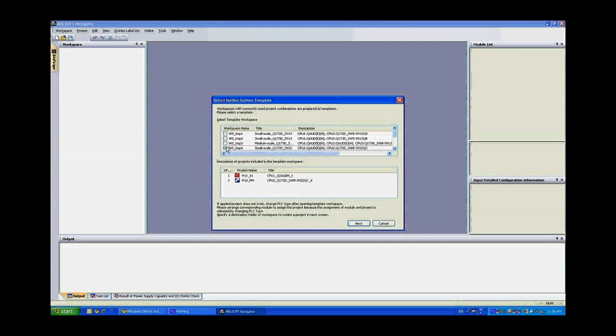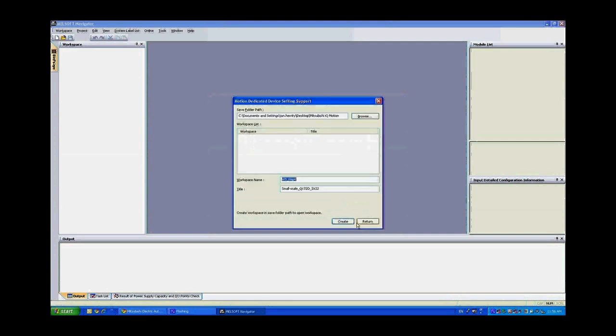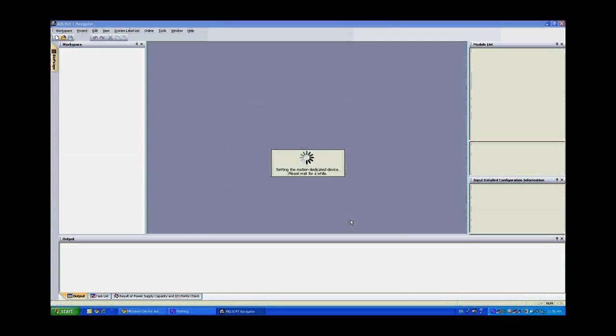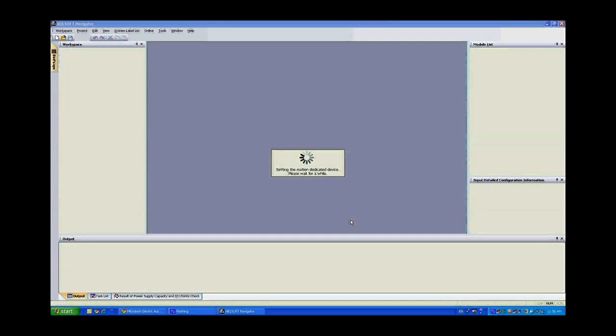WSTemp4 is a small-scale Q172D eight-axis motion controller template with a Q26UDH CPU. If I click next, this is going to generate two different projects, a PLC project and a motion project. It assigns all the dedicated labels for all the transfer between the motion controller and the PLC with automatic memory sharing included.